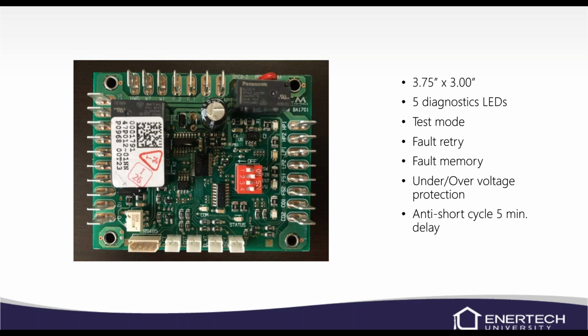Now, one thing I want to mention, that those lights are on doesn't necessarily mean, let's say the light right next to the low pressure is on, more than likely that means a low pressure, but it could also mean something else. You could have numerous lights on at the same time, one on, one flashing, and it'll tell you a code. We have up to 20 codes on this board to tell you what's going on with the unit. Now, there's only 5 lights, so that means that there could be multiple lights and multiple codes. So you kind of got to have the manual or it's on the unit as well.